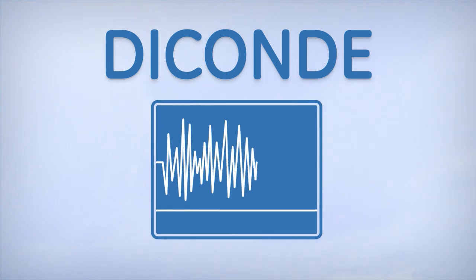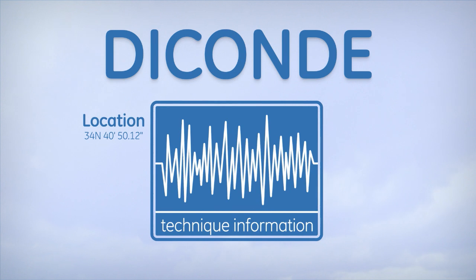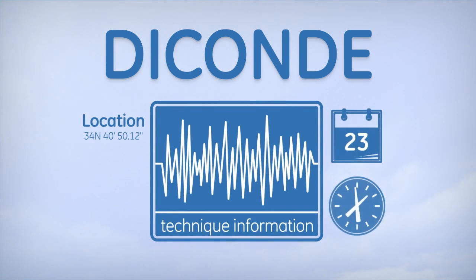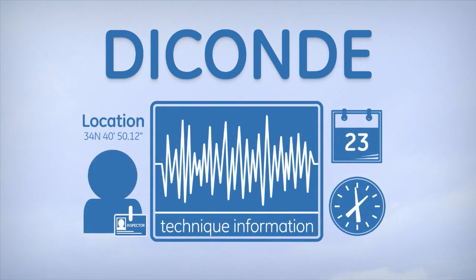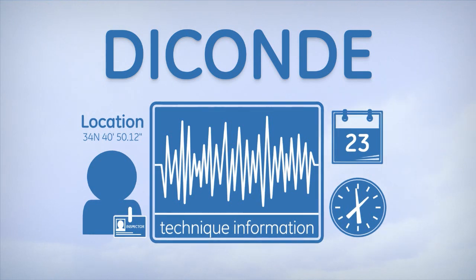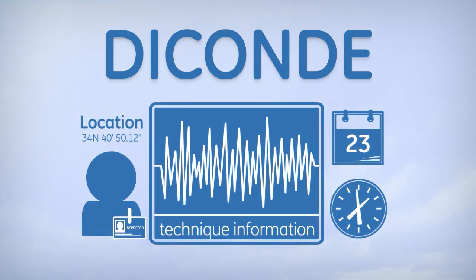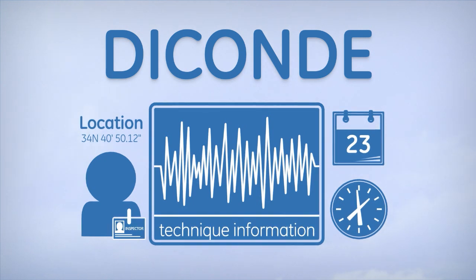DICONDE allows acquired data to be saved with context. All of the technique information is saved with the image, along with information on location, date and time, and the inspector who took the report. The information can then be included in any report generated, and it also allows database queries to be carried out on a variety of criteria.